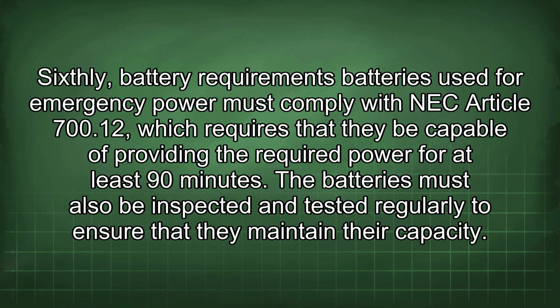Batteries used for emergency power must comply with NEC Article 700.12, which requires that they be capable of providing the required power for at least 90 minutes. The batteries must also be inspected and tested regularly to ensure that they maintain their capacity.